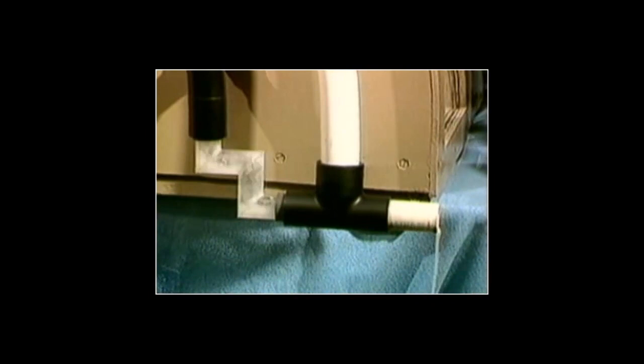One of the biggest problems with a condensate trap is that it catches debris and becomes blocked. This happens frequently, often after only 6 months of operation. The CostGard condensate drain seal inherently guards against such blockage. This special CostGard device, equipped with clear plastic elbows, shows why. Here soggy oatmeal is used to simulate the slime that often clogs drain lines and traps. Note the churning action produced by the air entering the device and the rapid passage of the debris.